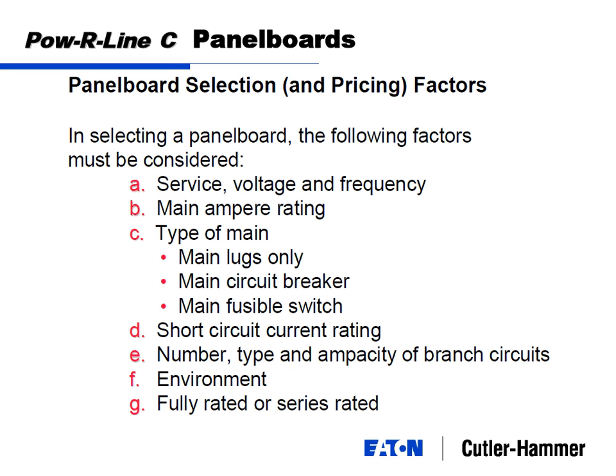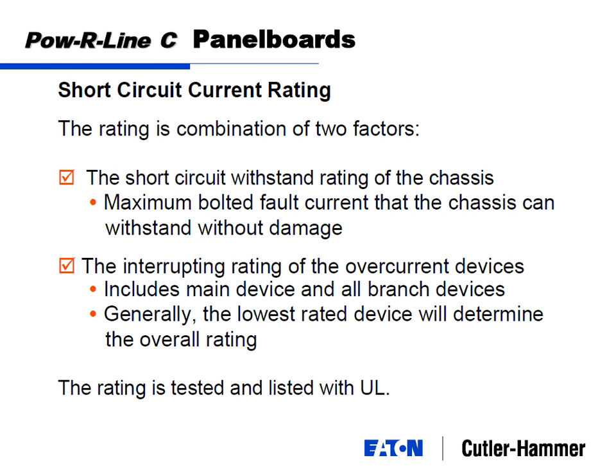The last one on the list is fully rated versus series rated, which we haven't talked about yet, and that's the asterisk question. So short circuit current rating, again, the short circuit withstand, that's how much the chassis can withstand. So if I've got 65,000 amps available fault current, you have to build the panel board chassis rated to 65 so everything stays together in one piece under a fault current condition. In addition to that, the interrupting rating of the overcurrent devices has to carry that short circuit current rating.